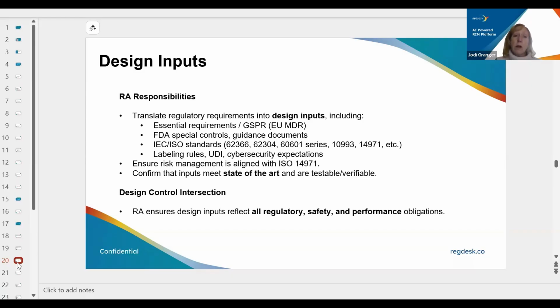So this area is where you start to get much more specific in terms of what the product is going to be required to meet. And again, I'll continue to stress that it's really important that these design inputs are thinking globally, because you don't want to have to repeat testing because you didn't factor in some requirement of a market that was on your target list, maybe not the top priority, but ultimately someplace that you want to go. So regulatory in this phase really helps to ensure that all regulatory, safety, and performance obligations are known to the team and fed into this design input phase.